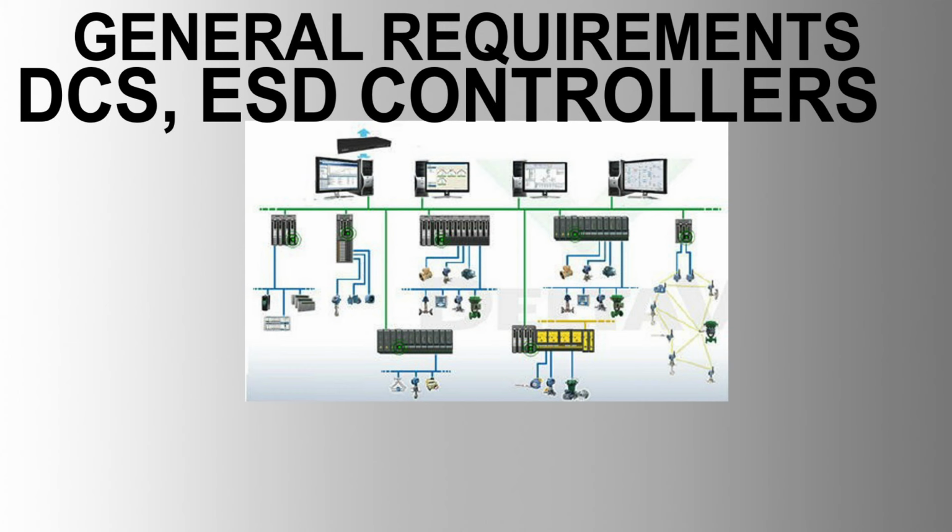3. Marshalling cabinets, design and configuration, equipped with field terminal blocks FTB and field termination assemblies FTA to mirror field junction boxes and I/O boards respectively. Used to cross-wire signals between FTB and FTA. Interconnection via pre-wired and pre-tested system cables with multi-way connectors. Field terminal blocks should be cage clamp interruptible or equivalent terminals with necessary polarity distribution, switching and protection, test points, and earthing systems.